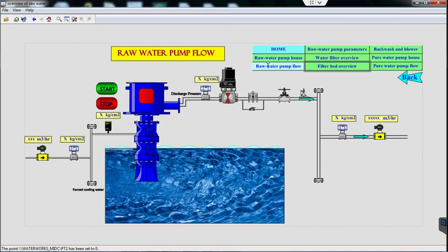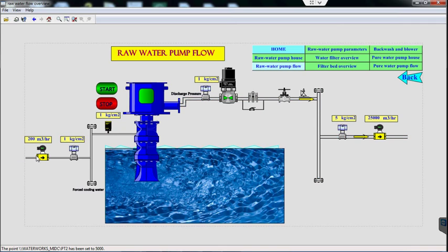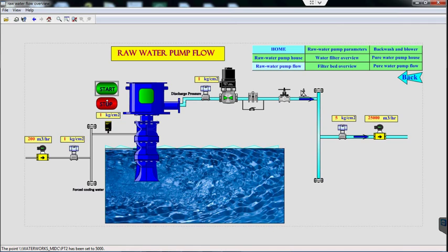Let us understand how raw water pump flow takes place. A raw water pump is provided with a force water line for pump cooling and bearing lubrication, and pure water is used for this application. A magnetic flow meter is provided on the common pipeline to measure the force water utility. A pressure transmitter is also provided to measure the force water pressure. A pressure switch is provided on each individual force water line to ensure the availability of force water when the raw water pump is in operation. When the pump is started, the discharge butterfly valve is also opened. If an adequate amount of pressure is developed, the pump will continue operation; otherwise it will automatically stop.